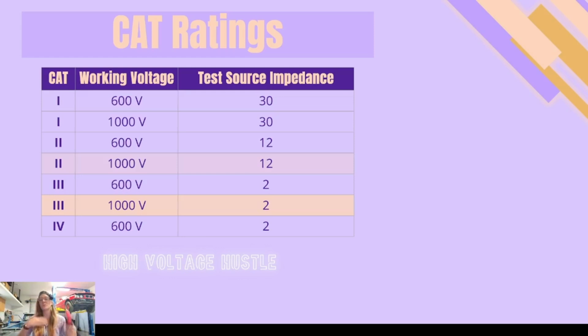So when we're working with high voltage systems, we want a higher cat rating so that we're protected from inrush current, spike current, lightning, direct shorts with really high current. If we have a meter rated to handle those spike currents, we're safe even while troubleshooting with that meter. That's why we invest in a nicer cat-rated meter.